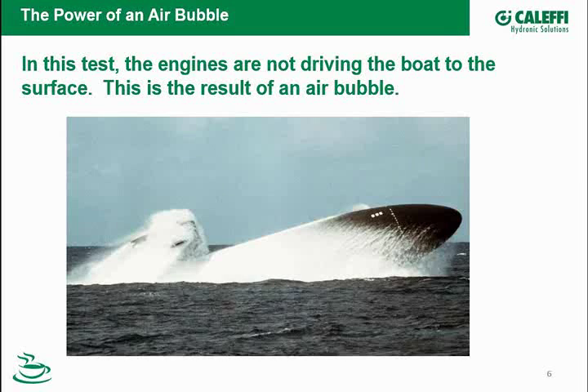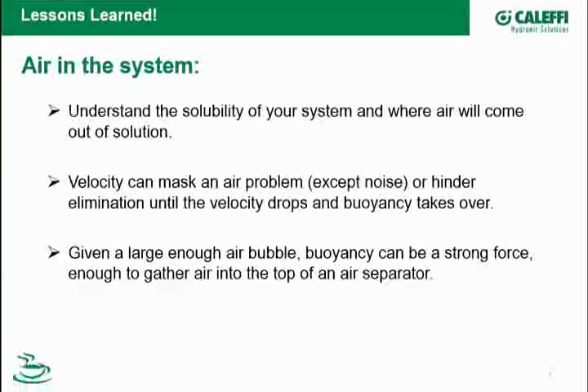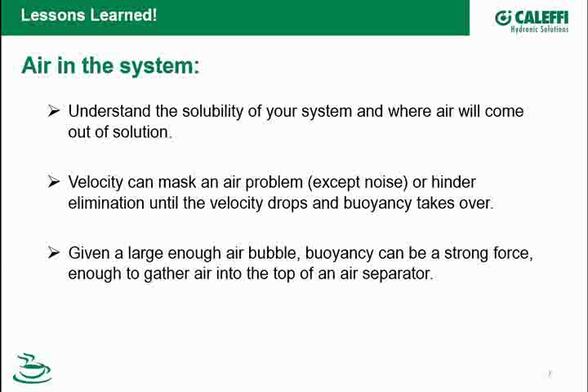Summarizing: you really have to understand solubility, because with air elimination, I have to put the air eliminator where the bubbles are coming out of solution. Velocity can mask an air problem — one thing it won't mask is noise. If I have an air problem, I will hear noise from those air bubbles moving through the system. Velocity can also hinder elimination if I'm moving the water too fast for proper separation, back to those dynamic forces. And if I can do something to increase bubble size, it will increase buoyancy and make it easier to do separation in a hydronic system.